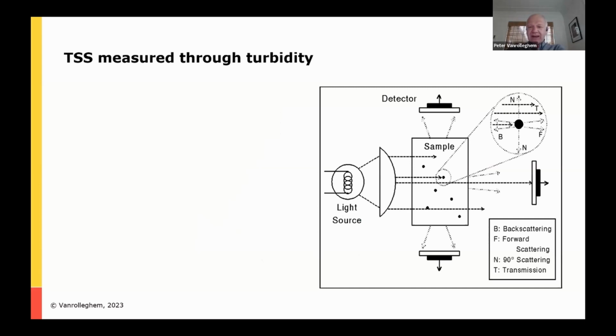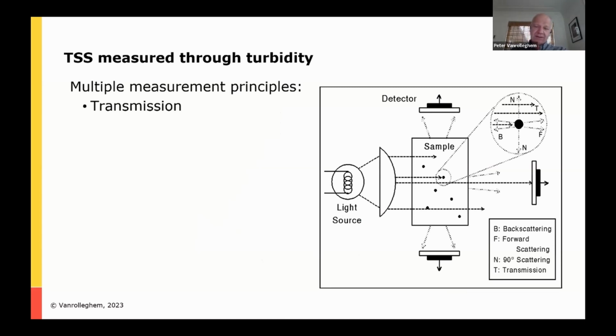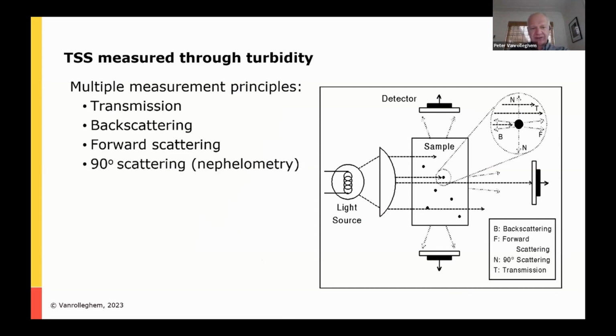This is a graph I made in 1993 in SlideWriter, and I still like it because it expresses quite nicely the different principles of turbidity meters. One is transmission - you measure the light that's getting through from the light on one side to the measurement device. You have backscattering, where particles backscatter light and you measure it when it's coming back. You may have forward scattering, which you can measure, and you might have the 90-degree scattering, which is called nephelometry - on 90 degrees you measure. All these principles have been shown to exist and work well in different situations in water systems.